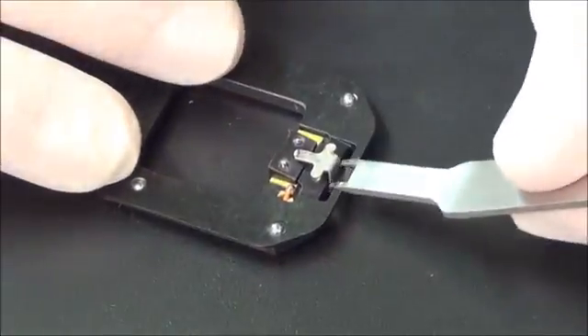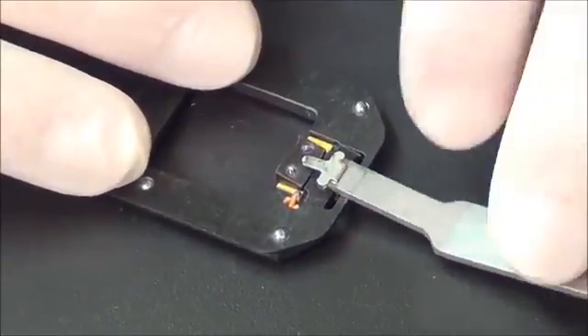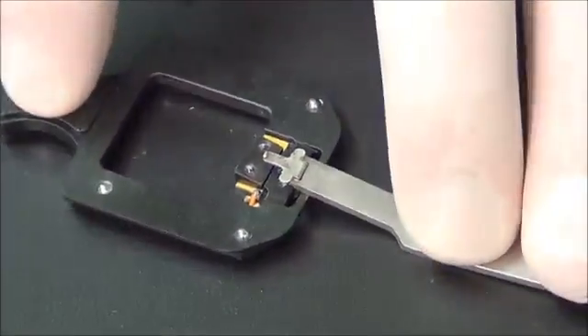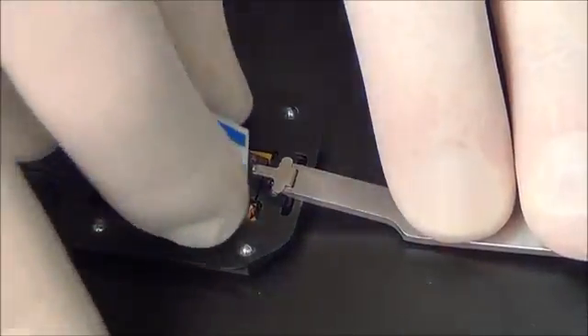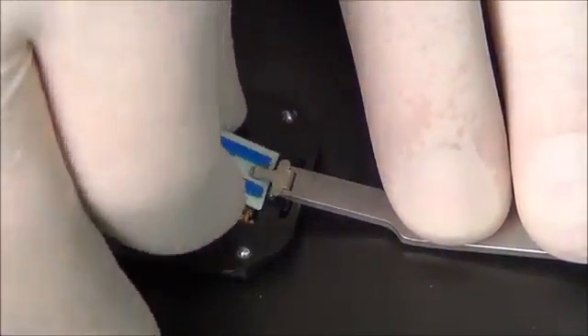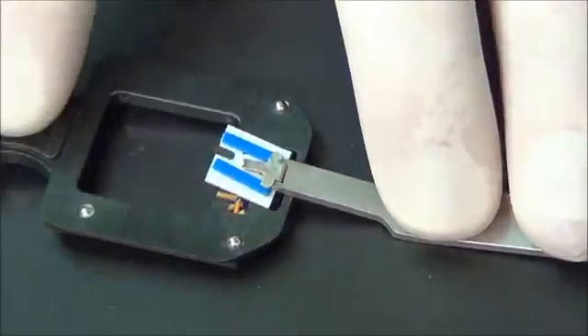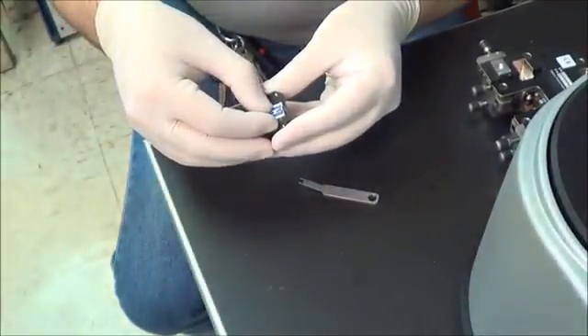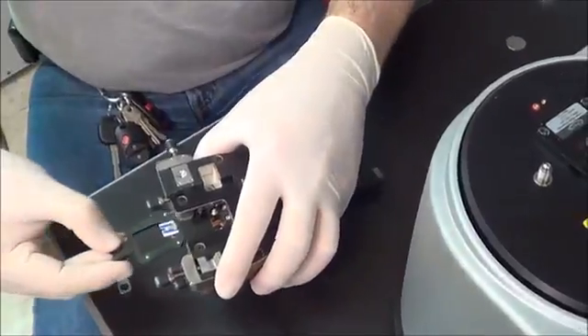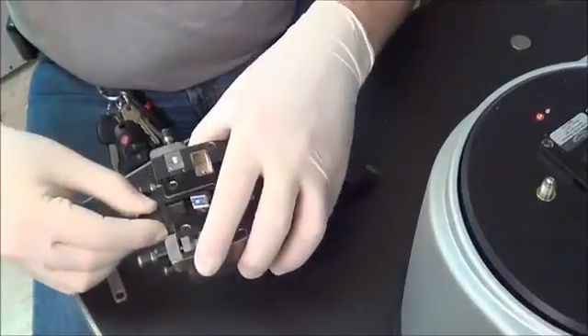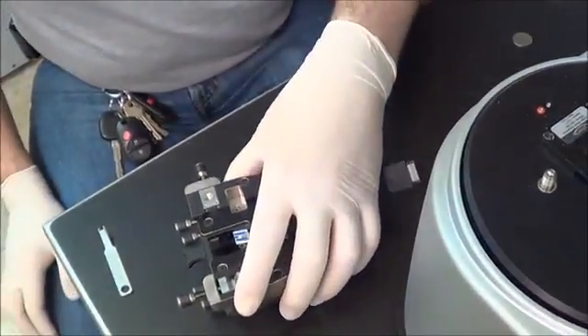To load a chip, we reverse the process. Remember, the cantilever is very fragile. The slightest touch of your finger will break it off, so you must be careful not to touch it at any point. To ensure that the chip is mounted properly, gently rock it back and forth. When you place the chip brace into the probe mount, you should feel it click into place.